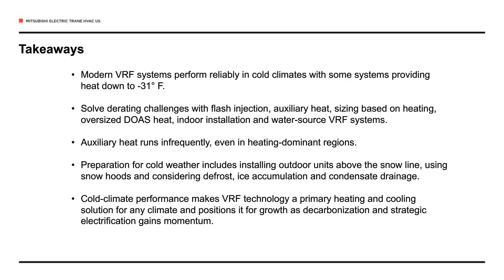Now, a few takeaways from today's webinar. Modern VRF systems offer cold climate capabilities far beyond older systems. With flash injection technology and today's compressors, VRF systems perform reliably in climate zones 1 through 6. Some systems provide heat down to minus 31 degrees Fahrenheit. We talked about some of the challenges of cold weather climates and the use of flash injection technology, auxiliary heat, DOAS systems, indoor installation, and water source systems.